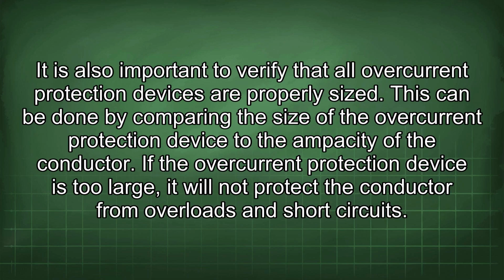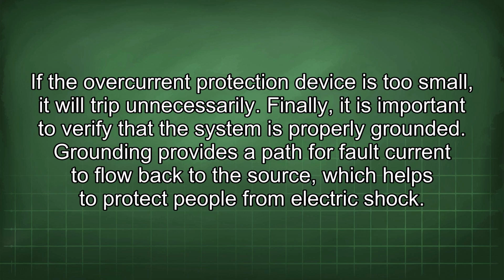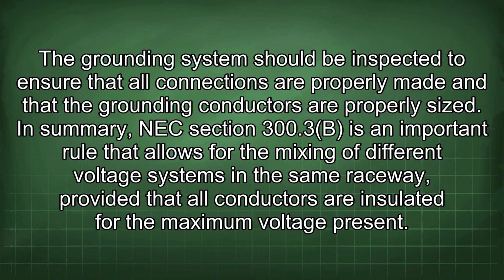It is also important to verify that all overcurrent protection devices are properly sized. This can be done by comparing the size of the overcurrent protection device to the ampacity of the conductor. If the overcurrent protection device is too large, it will not protect the conductor from overloads and short circuits. If the overcurrent protection device is too small, it will trip unnecessarily. Finally, it is important to verify that the system is properly grounded. Grounding provides a path for fault current to flow back to the source, which helps to protect people from electric shock.